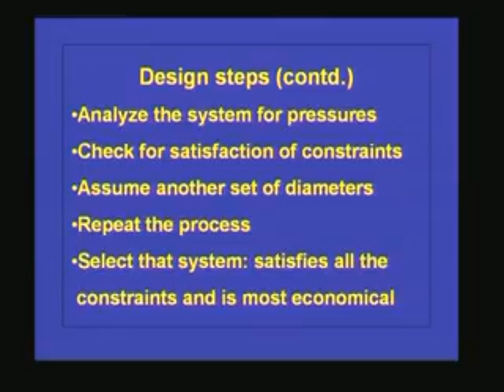Let us say first you choose a particular layout, and for that layout you choose the most economical diameters you can get. Then you change the layout, and for the second alternative layout, again you choose the optimal diameters that are possible. Like this you can have an outer loop for designing the layout itself. While doing that, you also have to talk to field engineers to see what field constraints may come in. You may give a particular route, but the field engineer will say it is not possible to acquire land for laying this pipeline, or that these are the problems I am going to have. So you have to incorporate those kinds of constraints also while designing water distribution networks.